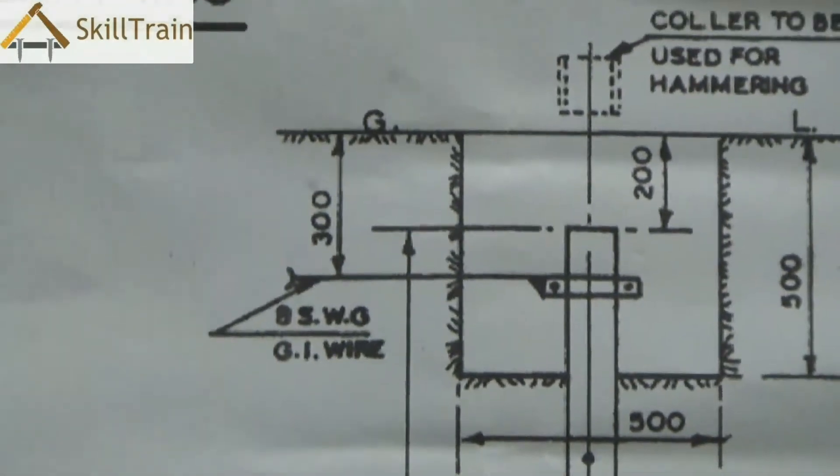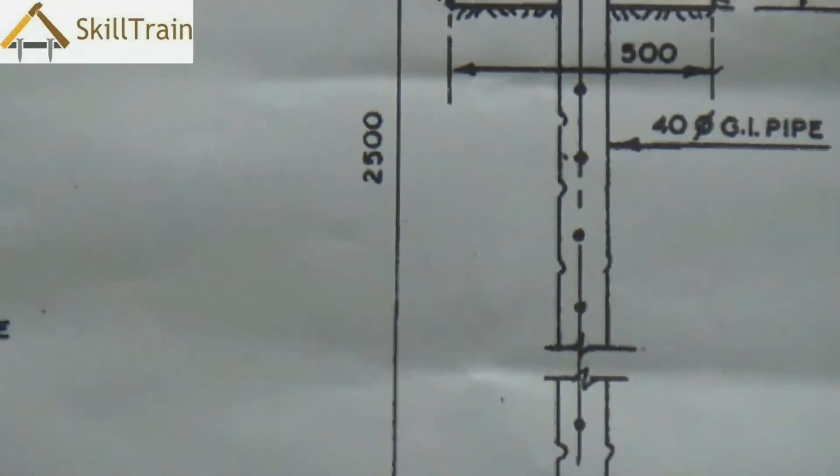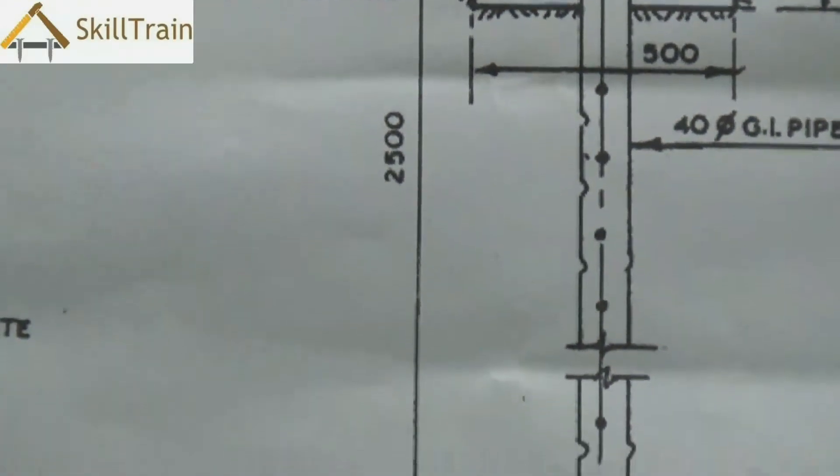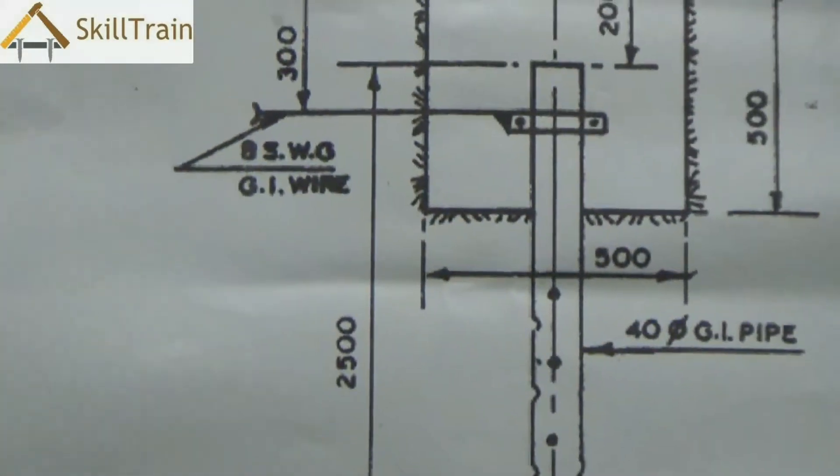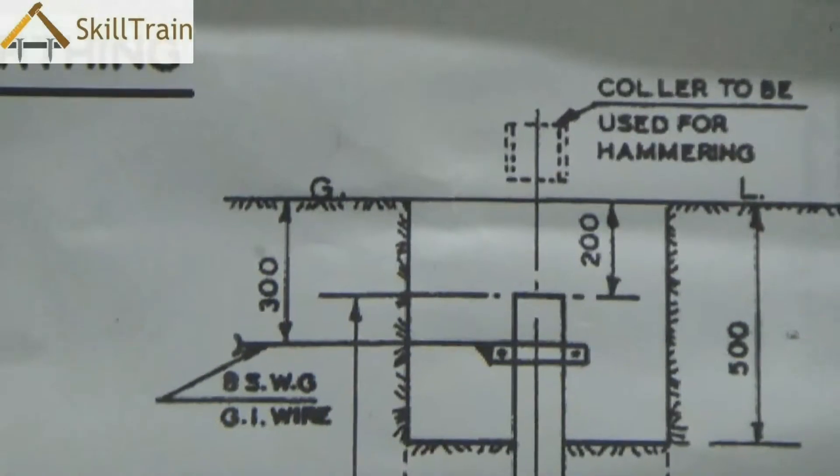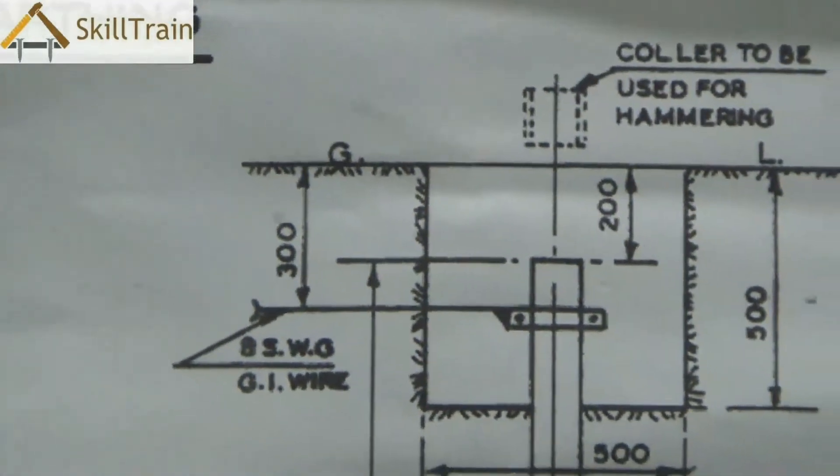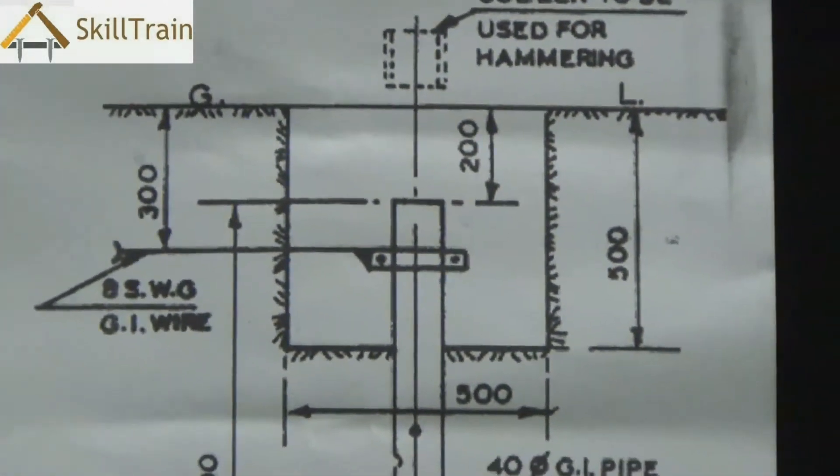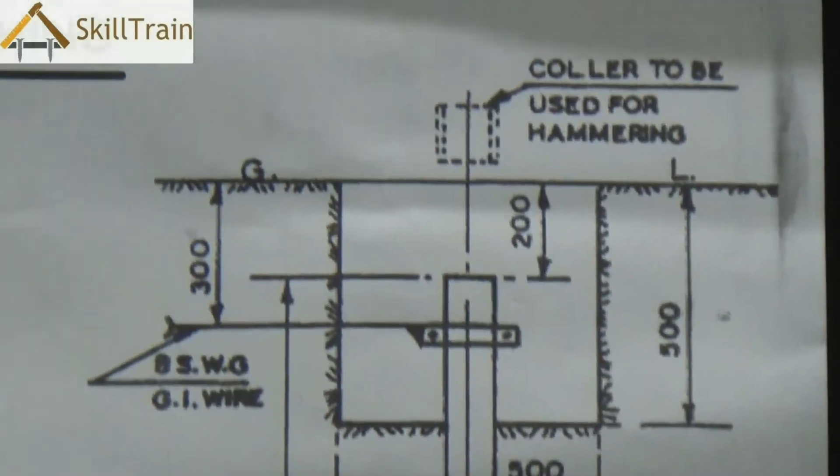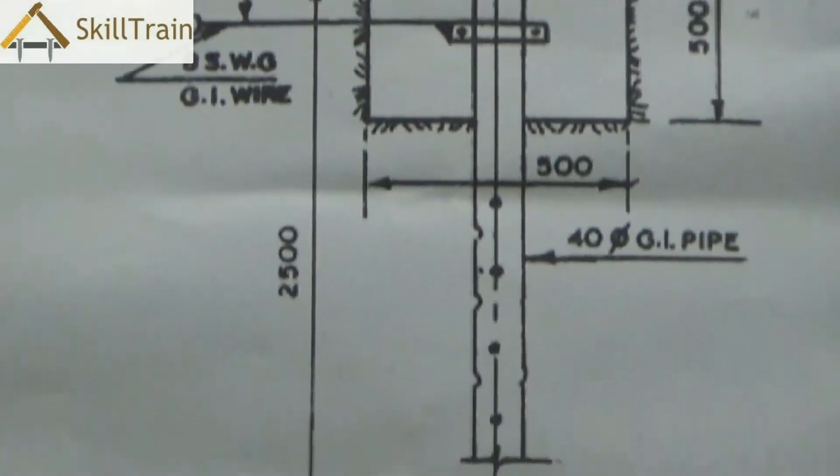In such a case we take a GI pipe about 40 millimeters diameter and thrust this pipe into the soil for at least four or five feet. It can be higher as well depending on how the soil is. Once you feed this in, there's a clamp on top where the GI wire is connected to the mains.